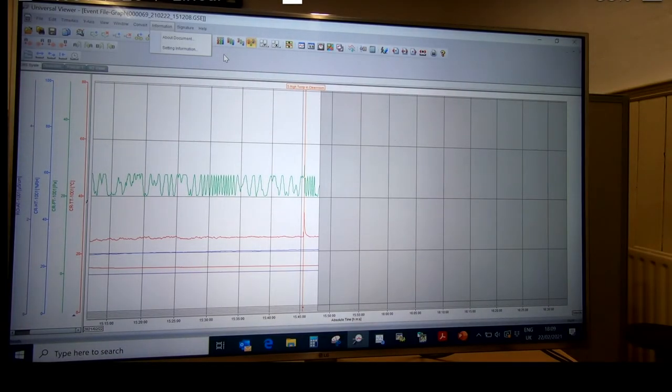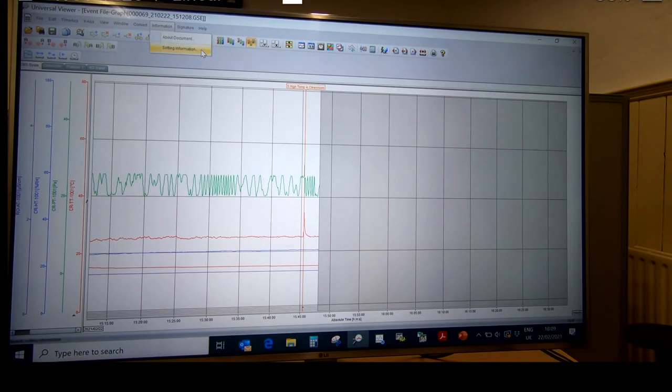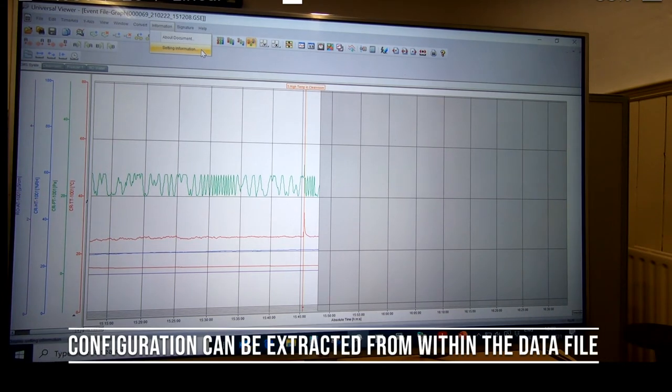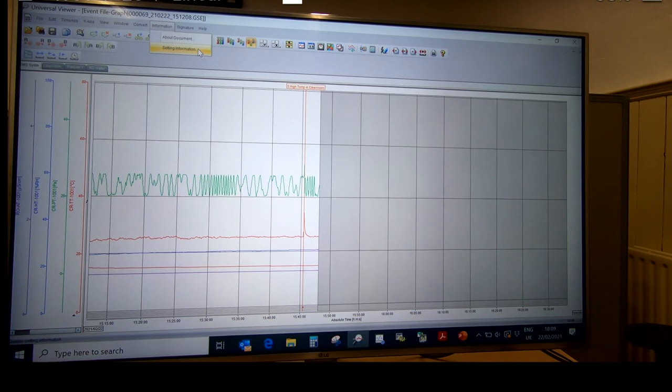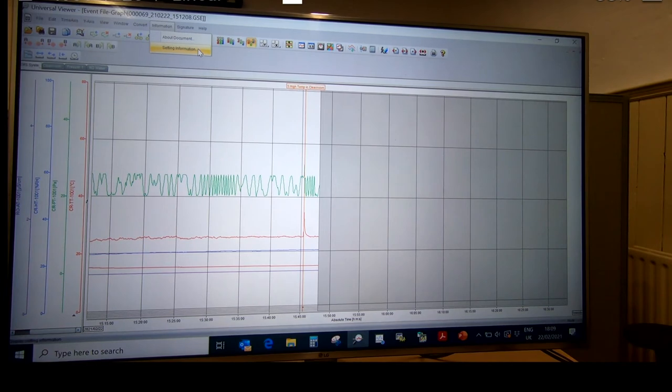Be it a batch record or 24-hour continuous monitoring for environmental monitoring systems, every file that's generated has that configuration embedded behind it and can be extracted from this location here from setting information. If you have the hardware configurator software, you click on that and it'll automatically bring you into that software and give you the configuration as it was applied when that last recording had happened.